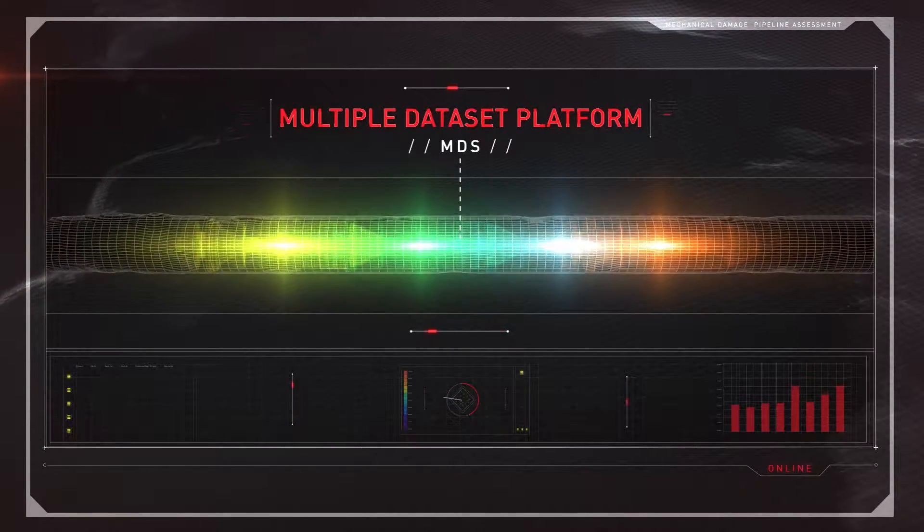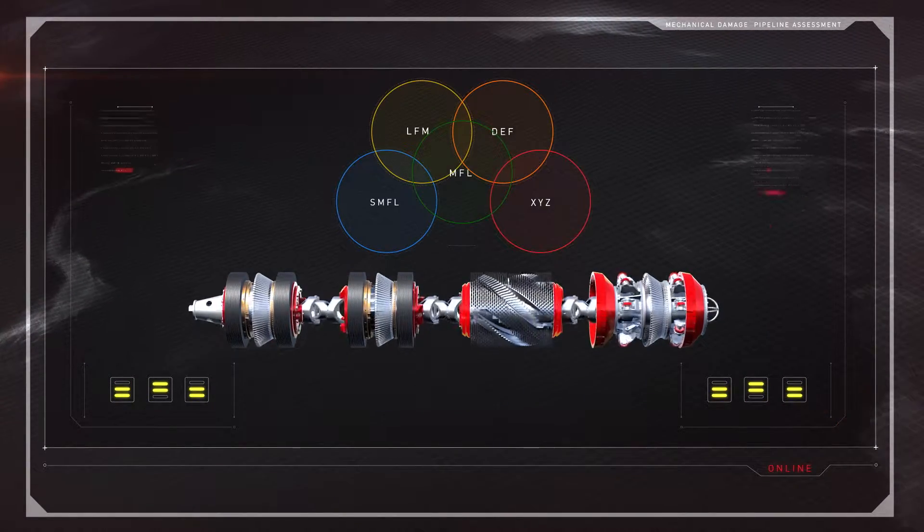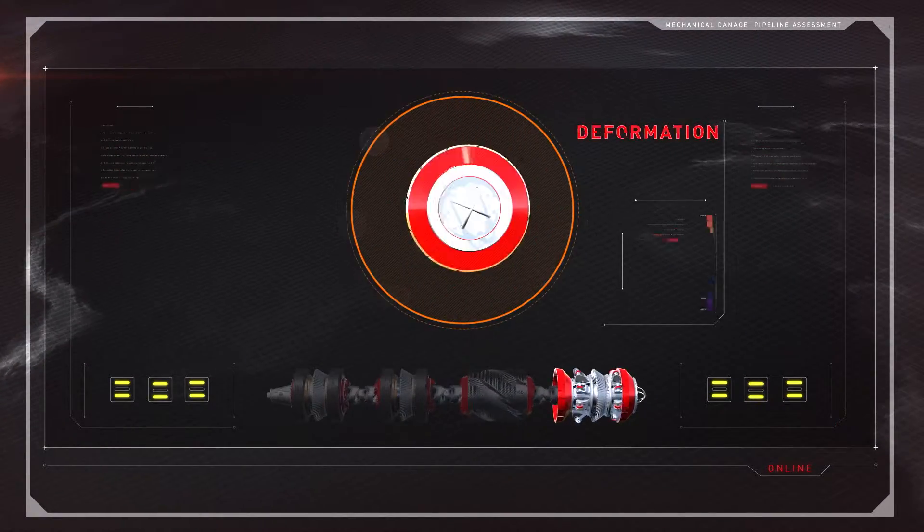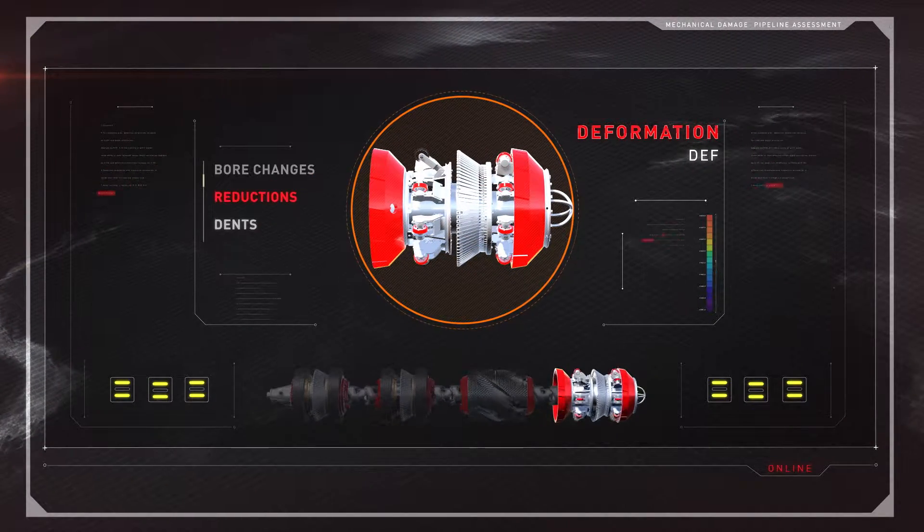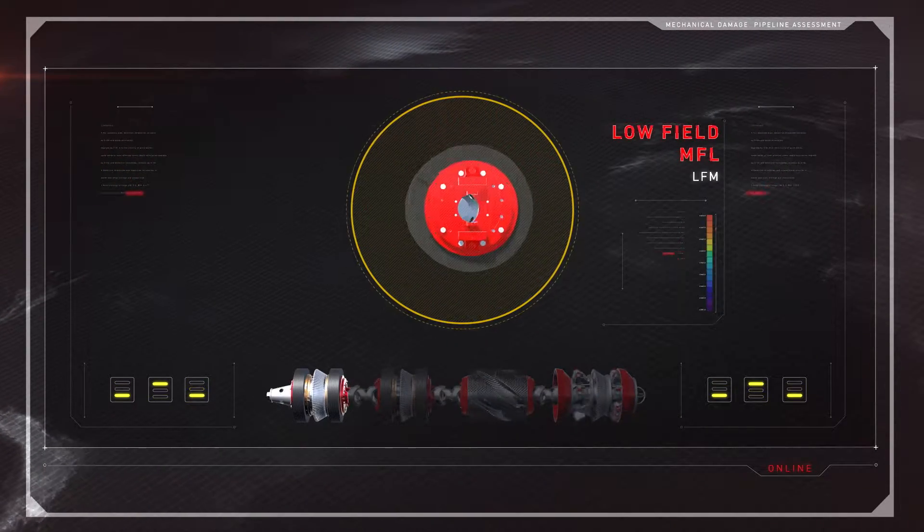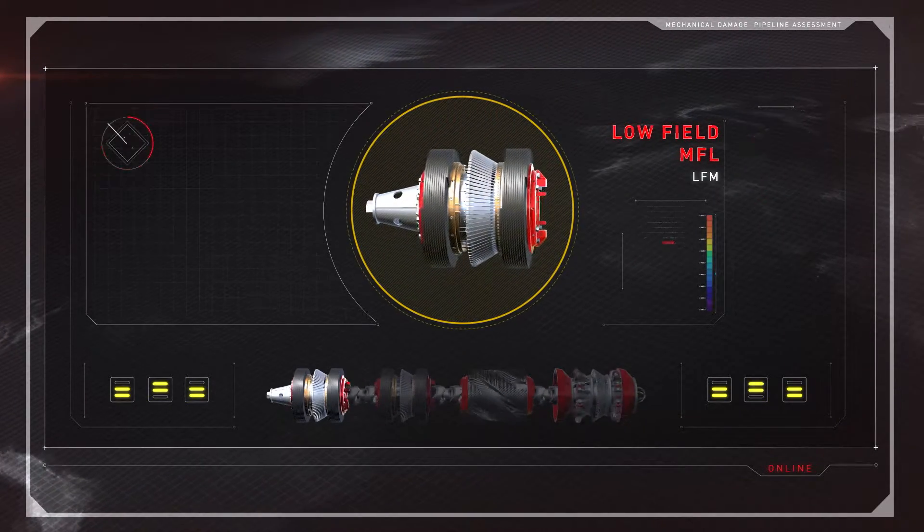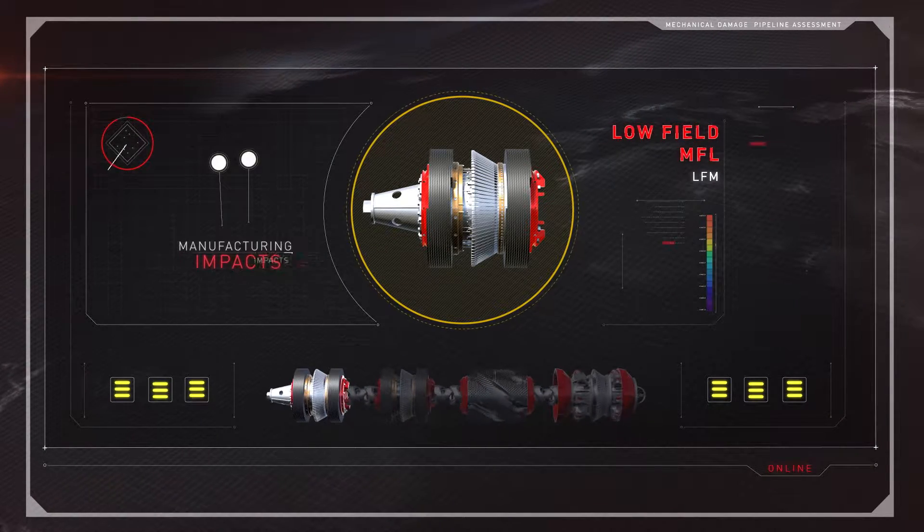Let's look at the technologies included in the MDS platform. Deformation technology detects the most minute bore changes and reductions, including dents. Low field magnetic flux leakage identifies permeability changes related to hard spots and pipe manufacturing impacts.